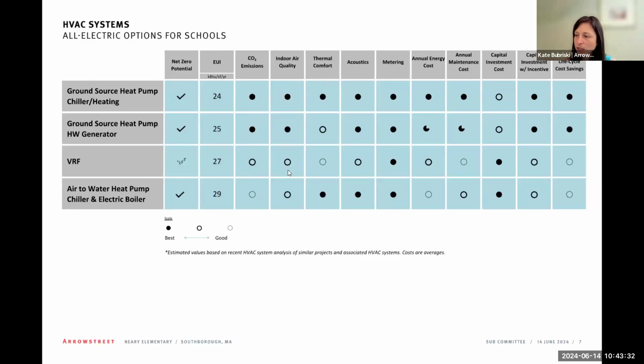We talked about the air quality and the thermal comfort. The air quality is derived through the displacement ventilation. For thermal comfort, the variation is that this one is full cooling and displacement, and the VRF doesn't have the displacement. Acoustics is also related to the displacement, which is quieter in terms of supplying air. The VRF also has active fan coils, so the fan coils and the motors in them add additional sound to the space. It's the ventilation being overhead and the fan coil that is why the acoustics score is lower for that system. Metering is essentially the same.